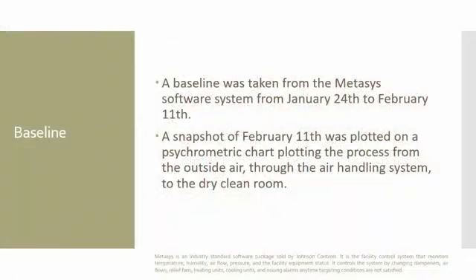A baseline trend of MAU2, DHU12, and DHU9 were taken from the Metasys software system from January 24th to February 11th. A snapshot of February 11th was plotted on the psychrometric chart, plotting the process from the outside air through the air handling system into the dry clean room.